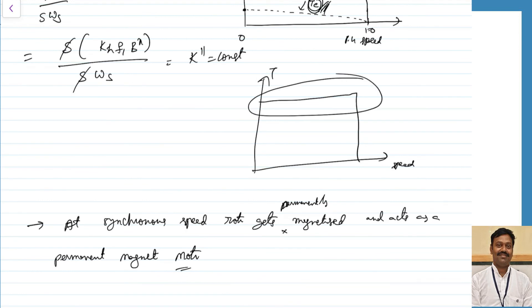The major advantage is that the torque is uniform. The rotor is made as smooth as possible, so the harmonic torques produced in induction motors due to slot harmonics are absent here, enabling completely silent operation. The torque is uniform from no load to full load, which is why it can pick up even high inertia loads at a faster rate to synchronous speed. By designing the torque to be two to three times full load torque, it can start from high inertia loads without any problem.